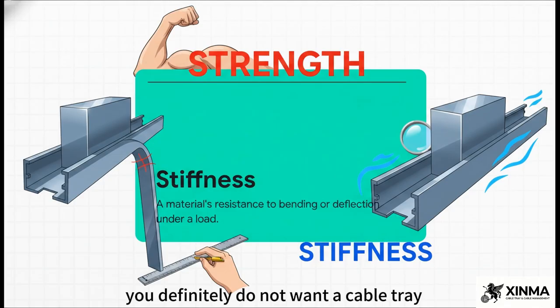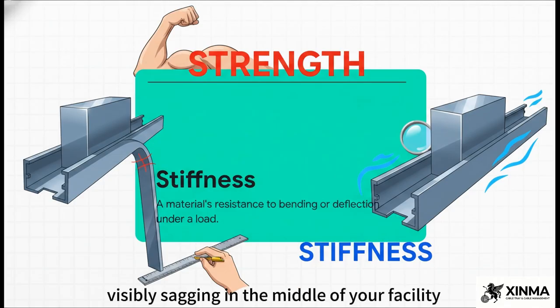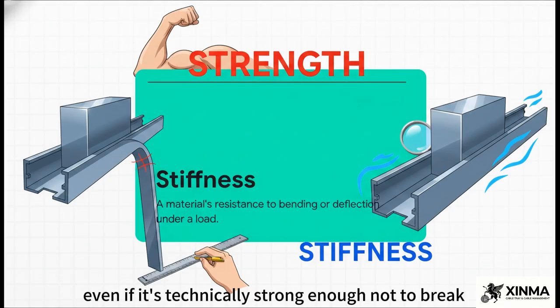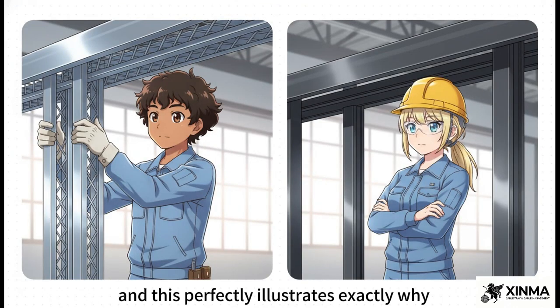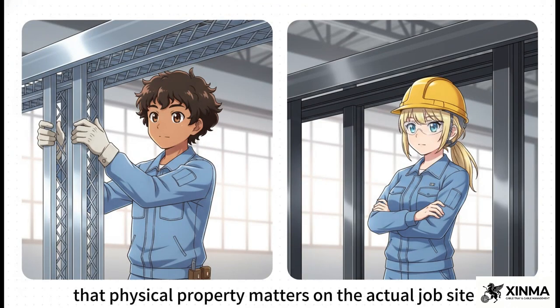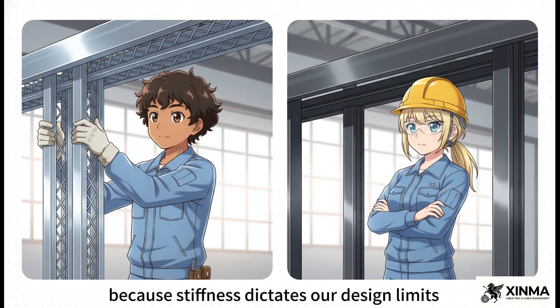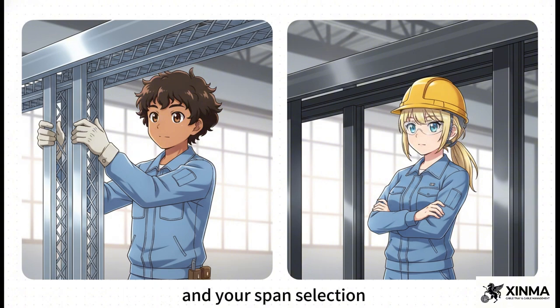You definitely do not want a cable tray visibly sagging in the middle of your facility, even if it's technically strong enough not to break. This perfectly illustrates why that physical property matters on the actual job site, because stiffness dictates our design limits, and it directly dictates your support spacing and span selection.